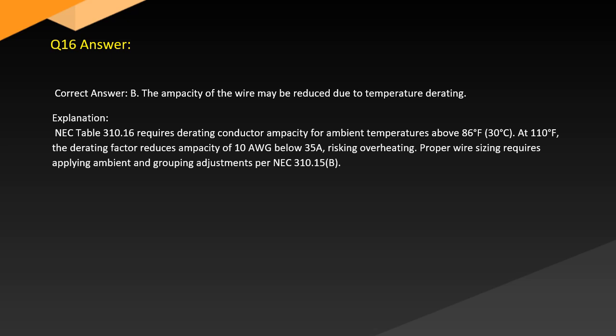Answer. Correct answer: B. The ampacity of the wire may be reduced due to temperature derating. Explanation. NEC Table 310.16 requires derating conductor ampacity for ambient temperatures above 86 degrees F, 30 degrees C. At 110 degrees, the derating factor reduces the ampacity of 10 AWG below 35 amps, risking overheating. Proper wire sizing requires applying ambient and grouping adjustments per NEC 310.15(B).